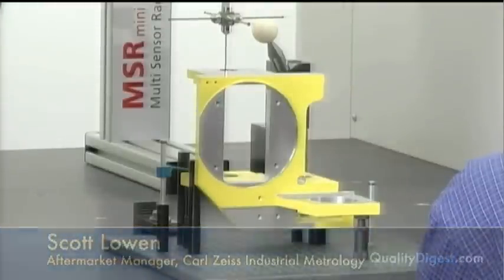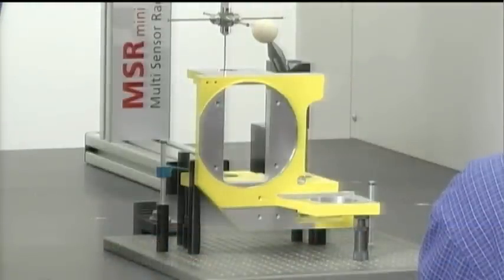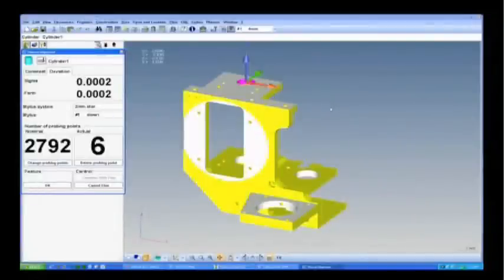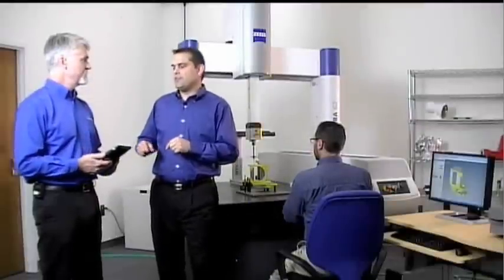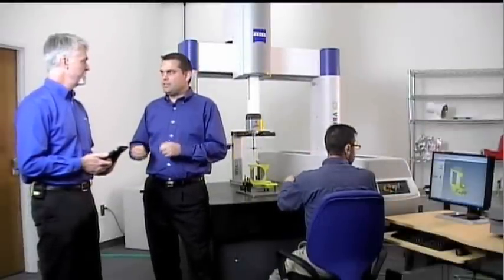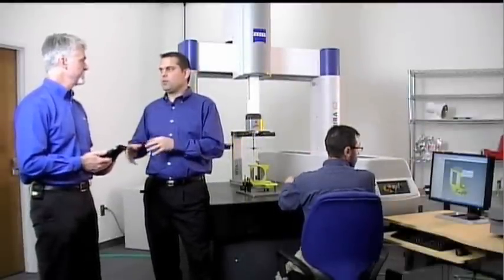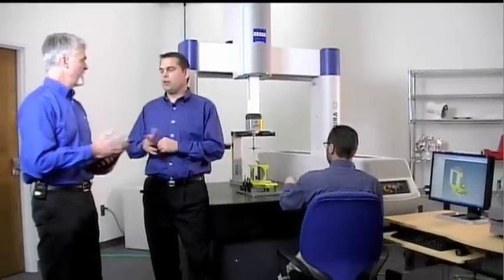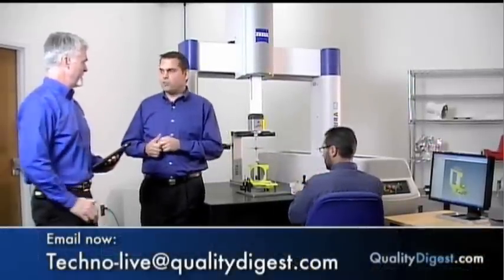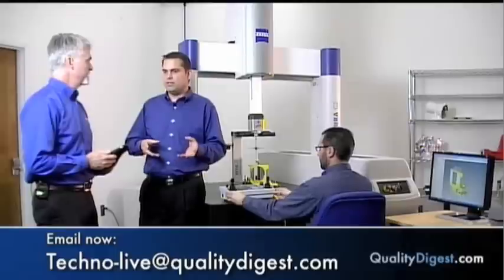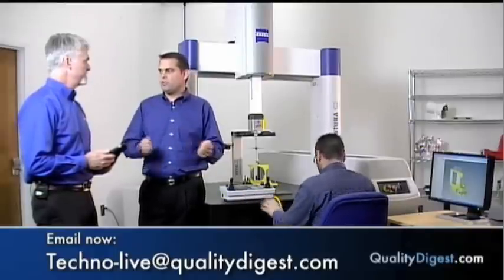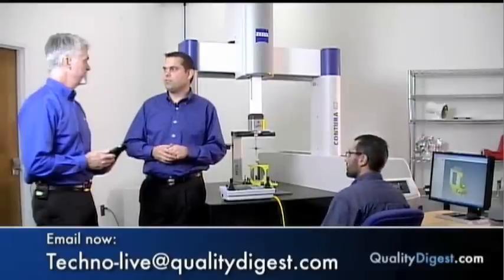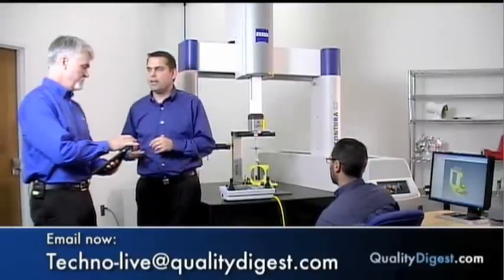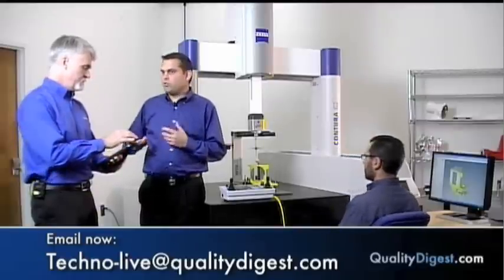Okay, we have another question here from Xavier in California. Who calibrates the machine after it's upgraded with Calypso? First of all, what does he mean by that? Probably the concern there is the data, the correction data, sometimes resides in the operating system. So the volumetric error correction stuff? Yeah, the correction data. So it may actually be in the software. The software does often more than just prepare measurement plans. It is also managing the correction and the accuracy of the machine. So the question is who calibrates it.